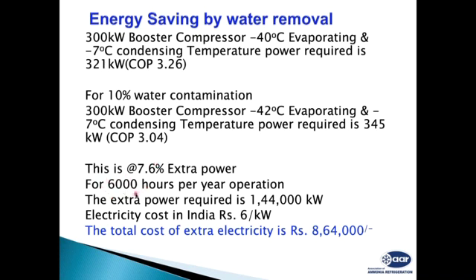If our plant is running for 6,000 hours in a year, the extra power required will be around 1,44,000 kilowatt hours. In India, the electricity cost we have assumed throughout this presentation is 6 rupees per kilowatt. The cost of the total electricity due to the water in a plant will be around 8,64,000 Indian rupees. This clearly shows that it's a huge cost. And while calculating this, we have not considered other effects, which means the corrosion in the plant, the failure of the components, the frequent changing of the oil. If you add all those costs, this becomes very high.